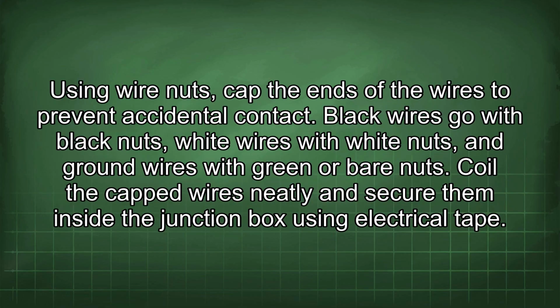Using wire nuts, cap the ends of the wires to prevent accidental contact. Black wires go with black nuts, white wires with white nuts, and ground wires with green or bare nuts. Coil the capped wires neatly and secure them inside the junction box using electrical tape.